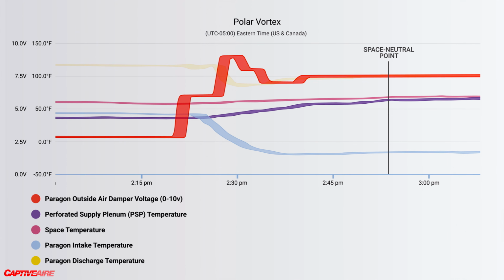So this shows now, once I started adjusting, this red value is that outside air damper. You can see I actually brought it too much positive, started dialing it back, and I fine-tuned it up, down until we got right to that balance point. And then with that, I wanted to also make sure that my discharge temps were adequate. So at this final point here, we can see my discharge temps were still able to hit, even with that added outside air over what the unit was designed for, we were still hitting around 100 degrees. So this space in the end had no compromises.